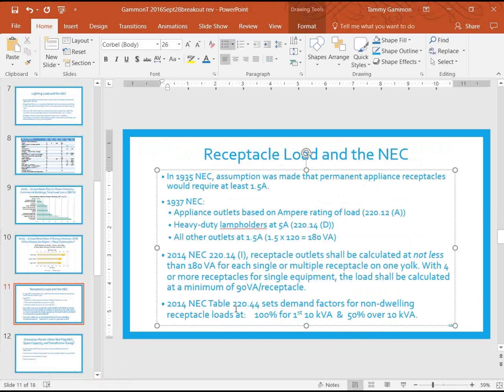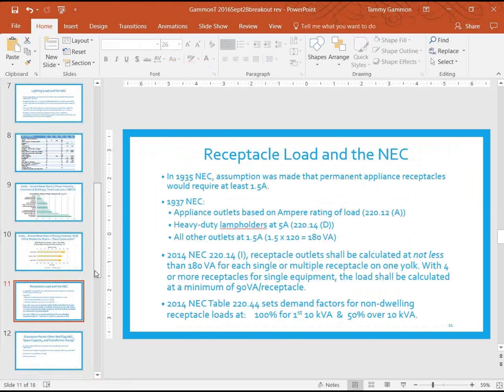And then Table 220.44 sets demand factors for non-dwelling receptacle loads at 100% for the first 10 kVA and 50% over 10 kVA. And that's another reason I was really interested in this project when I saw the RFP, because I've had my own experiences with receptacle loads.